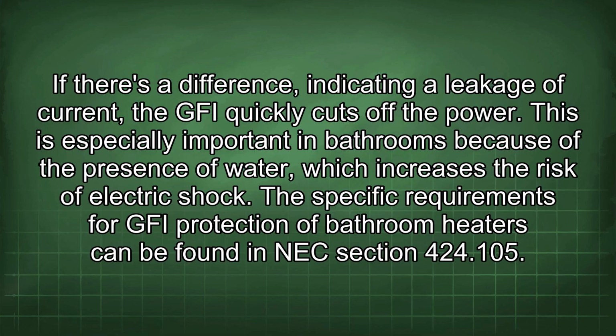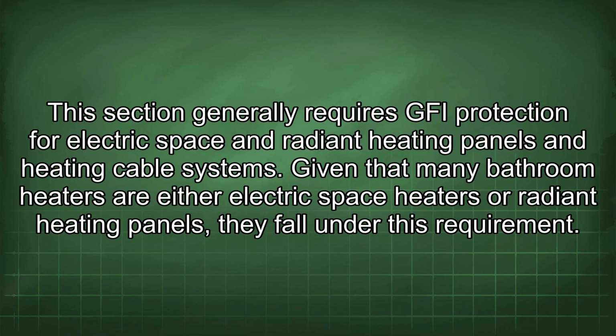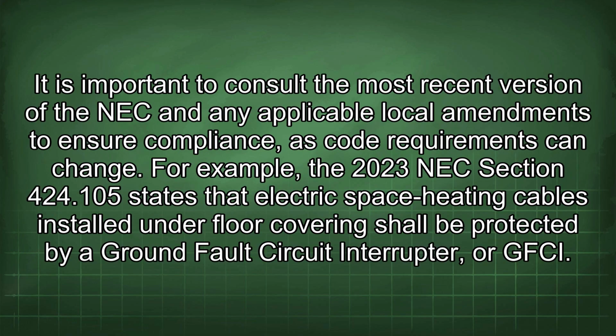The specific requirements for GFI protection of bathroom heaters can be found in NEC section 424.105. This section generally requires GFI protection for electric space and radiant heating panels and heating cable systems. Given that many bathroom heaters are either electric space heaters or radiant heating panels, they fall under this requirement. It is important to consult the most recent version of the NEC and any applicable local amendments to ensure compliance, as code requirements can change.